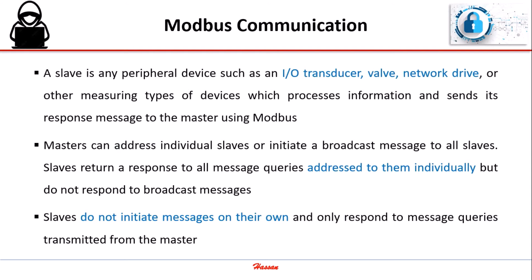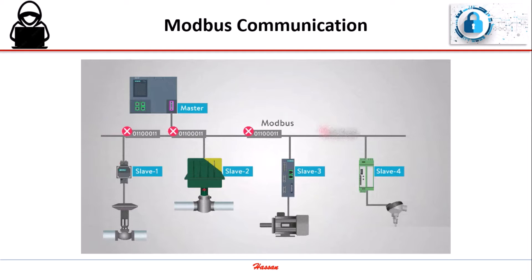A slave is any peripheral device such as an I/O transducer, valve, network drive, or other measuring device which processes information and sends its response message to the master using Modbus. Masters can address individual slaves or initiate a broadcast message to all slaves. Slaves return a response to all message queries addressed to them individually but do not respond to broadcast messages. Slaves do not initiate messages on their own and only respond to message queries transmitted from the master.